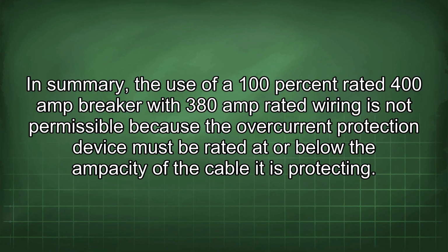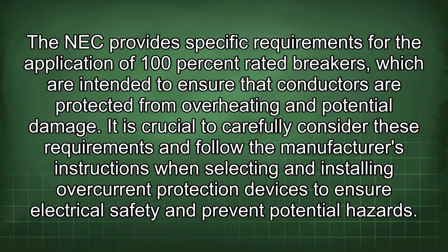In summary, the use of a 100% rated 400 amp breaker with 380 amp rated wiring is not permissible because the overcurrent protection device must be rated at or below the ampacity of the cable it is protecting. The NEC provides specific requirements for the application of 100% rated breakers, which are intended to ensure that conductors are protected from overheating and potential damage. It is crucial to carefully consider these requirements and follow the manufacturer's instructions when selecting and installing overcurrent protection devices to ensure electrical safety and prevent potential hazards.